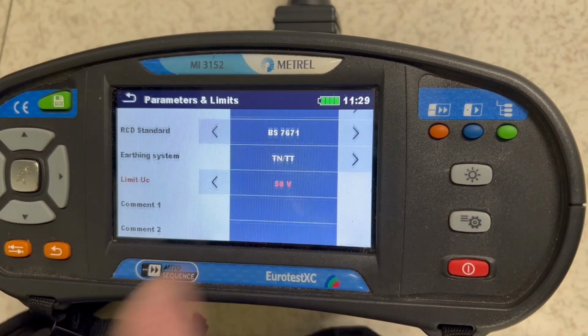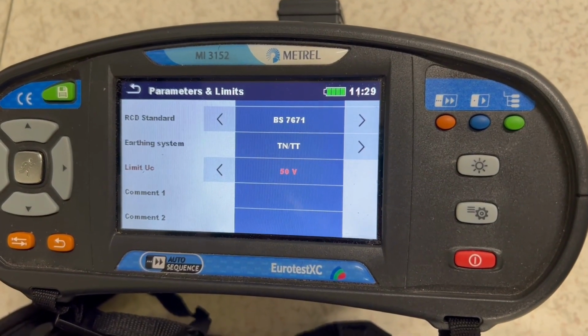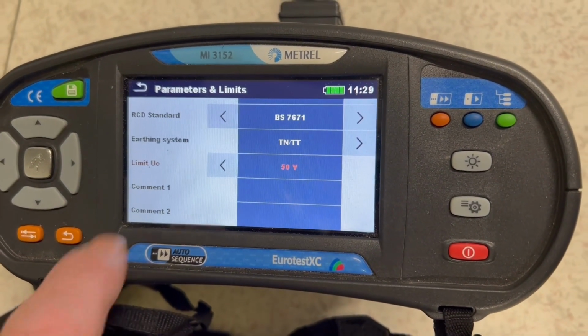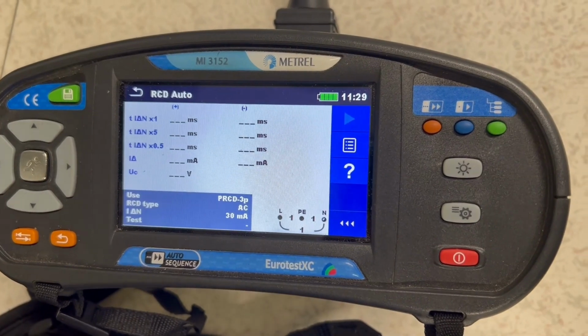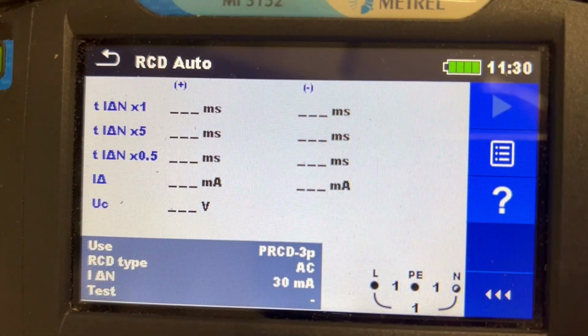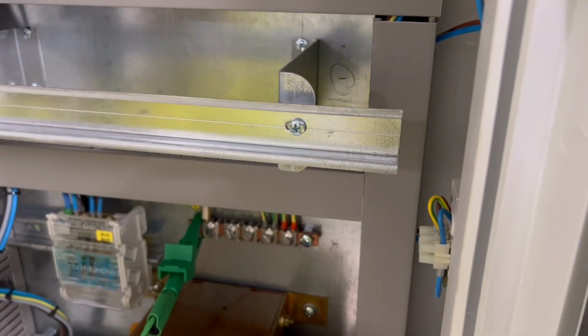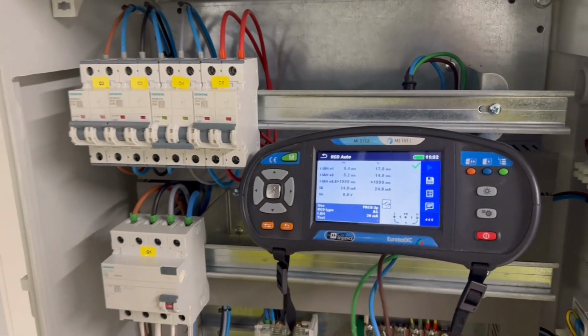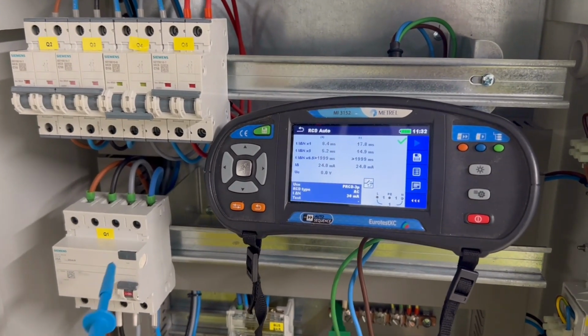As I said before, we are testing to 7671 on this installation, and our earthing systems are TN. So these are the group of tests. We've got positive and negative sequences, so the positive part of the cycle and the negative part. So we've got a test at times 1, times 5, 0.5, and we've also got a ramp facility on the positive and negative cycles. Okay, let's show you how this test works.